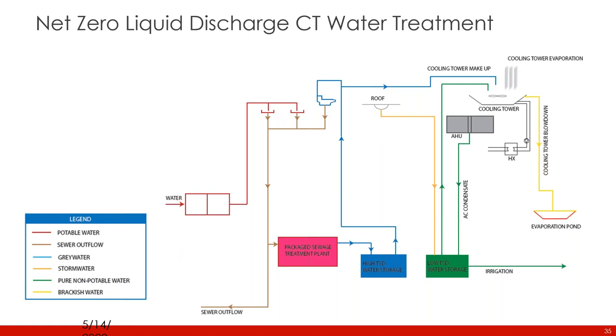So the second strategy is to control the pH of the water in the cooling tower in the range of 9 to 10, which is very basic. And what this does is this typically causes the ammonium ions to develop into ammonia gas, where it will be off-gassed from the water. The reason you're worried about that is because ammonium ions will attack any solid copper in the system. So if you have any copper or brass fittings, ammonium ions will attack that. But if you get rid of the ammonium ions by off-gassing ammonia, then in fact, you'll not have that problem.